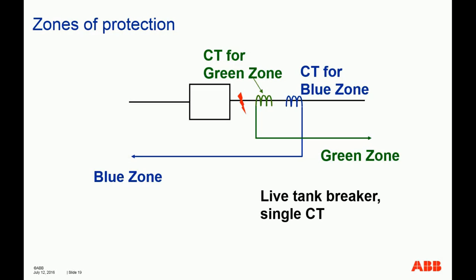So the solution again for that is, once the breaker is open, you can remove the two CTs. Not the physical connection, but inside the relay, there's a certain algorithm you can use to tell the relay to ignore the connection of these two CTs. As soon as the breaker is open, remove these two CTs, and you can actually speed up the trip of the green zone relay, because once you remove this connection, the protection for the green zone will operate and clear this fault. Okay. And similarly, if this breaker is operated in the normally open position, then you should remove these two CT sources to the protective relay.